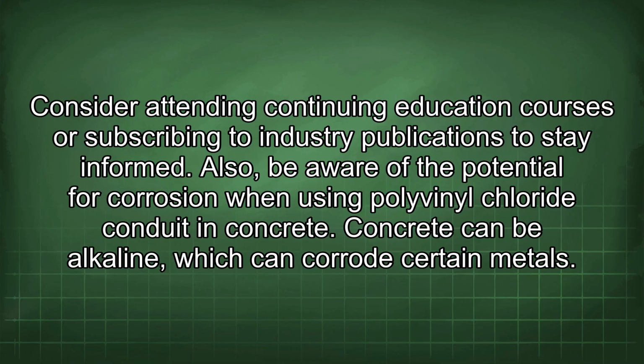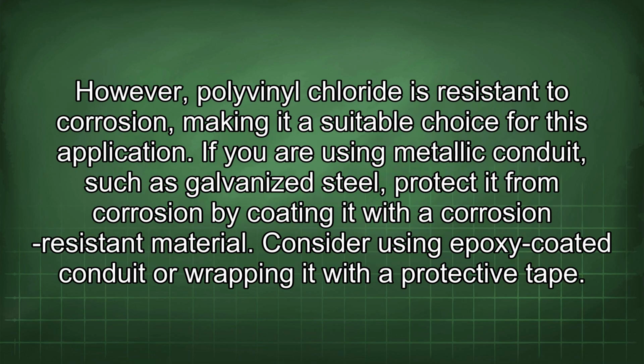Also, be aware of the potential for corrosion when using polyvinyl chloride conduit in concrete. Concrete can be alkaline, which can corrode certain metals. However, polyvinyl chloride is resistant to corrosion, making it a suitable choice for this application. If you are using metallic conduit, such as galvanized steel, protect it from corrosion by coating it with a corrosion-resistant material. Consider using epoxy-coated conduit or wrapping it with a protective tape.